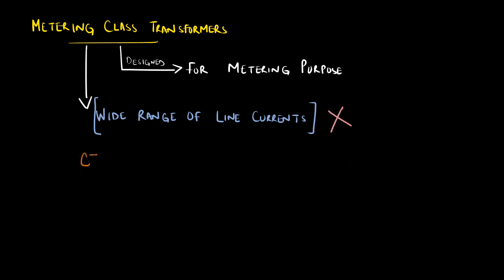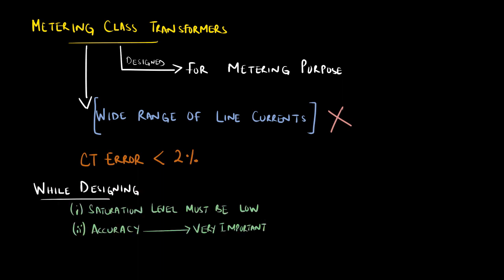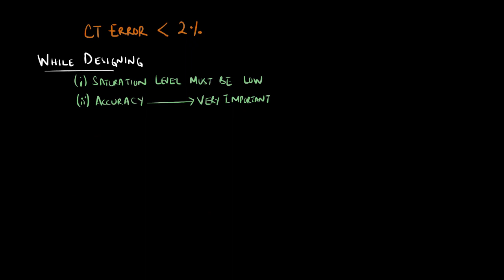A wide range of current is not required for metering class CTs. However, high accuracy is required to avoid CT error. We must carefully size metering class CTs because it can become inaccurate when the load current exceeds the CT rating.